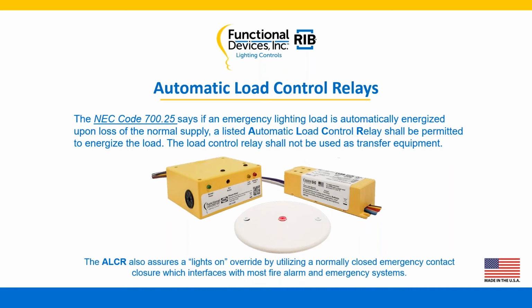What they end up doing is pushing the test button, the test load button will come on, and it works from there. You go to the right-hand side, you've got the same four buttons up here on the top, this being a ballast fixture mount type of ALCR. And then we've got what we call a remote test button. This remote test button is a little unique compared to our competitors. What's really nice about it is the fact you don't have to have high voltage going to it. It's a dry contact. It can sit alongside the fixture. And really what's nice about it is you save on material and labor cost when installing. That's a key feature for us, and we're very proud of that.